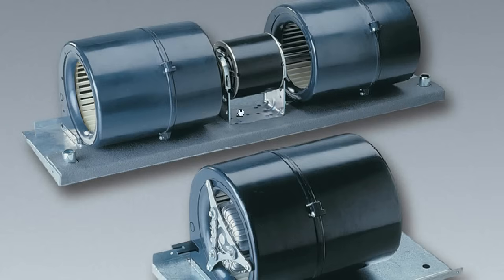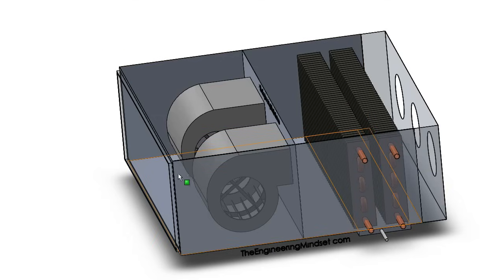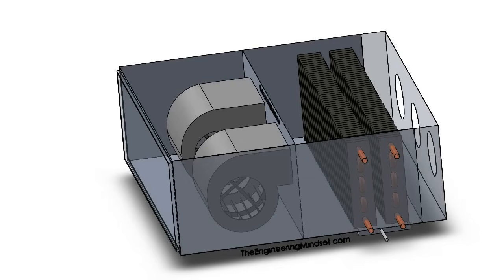In the real world, the fans look something like this — here we've got two fan chambers mounted to one motor, and here a single fan with its own motor. The heating and cooling coils don't necessarily have to be after the fans; it varies by manufacturer. The coils could also be before the fans, so air passes through the filter, over the coils, and is then sucked by the fans and pushed out. You may also find a refrigerant-based AC unit doing the same job as the chilled water coil, and the heating coil could be electric — it depends on the size and location of the fan coil unit. The water-type coil system is very common in large buildings, especially offices.